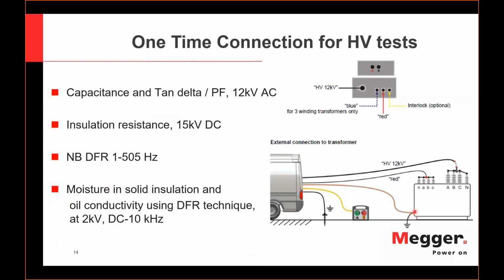First of all, of course, is the protective ground that connects the grounded tank of the equipment with the vehicle. We also use a second ground reference point, because that cable can be very long, 50 meters, and there could be potential differences between this remote ground and the near ground, close to the chassis of the car. So the electronic circuit will always monitor the voltage difference between those two ground points and switch off the equipment if necessary. Then you make the typical connections that are needed for the HV test. HV test means insulation tests.